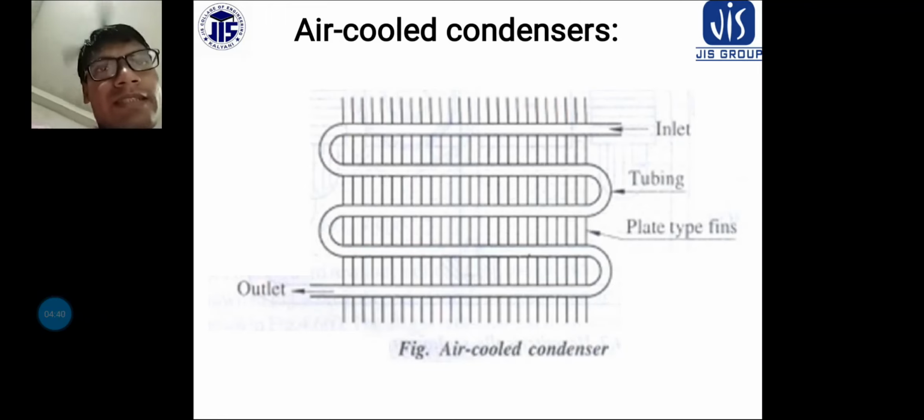The heat rejection factor of a plant varies with the operating condition of the plant, that is the evaporator temperature and the temperature of the condensing medium. So to obtain optimum performance from a plant, the high pressure should be kept reasonably low by maintaining the condenser tubes and the condenser water system clean.